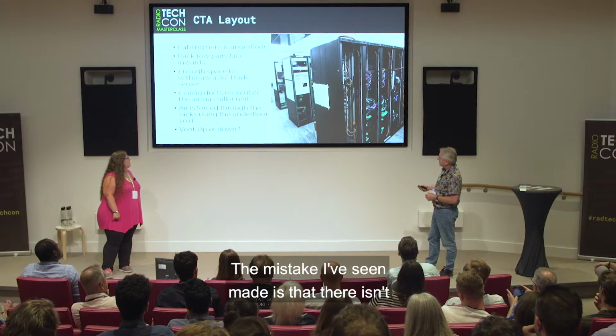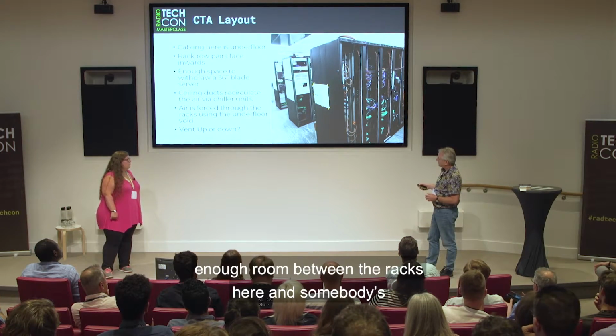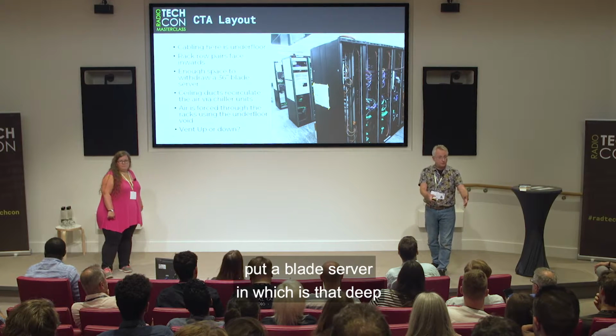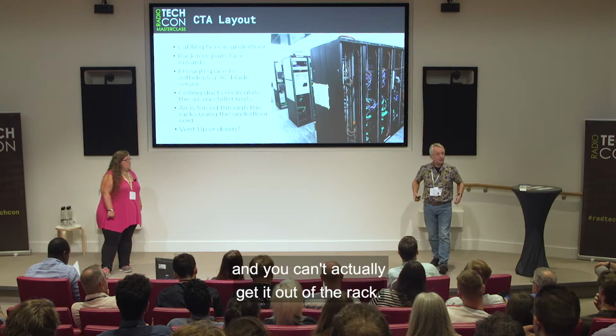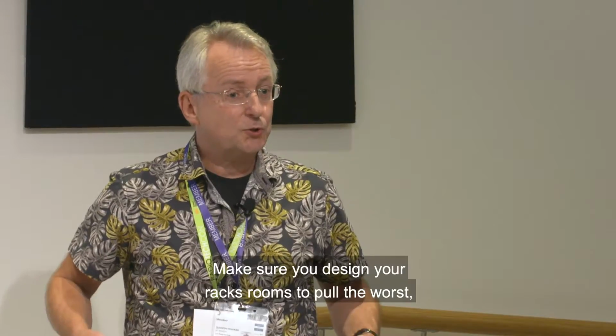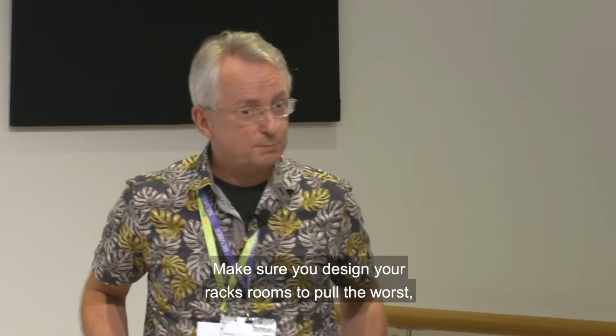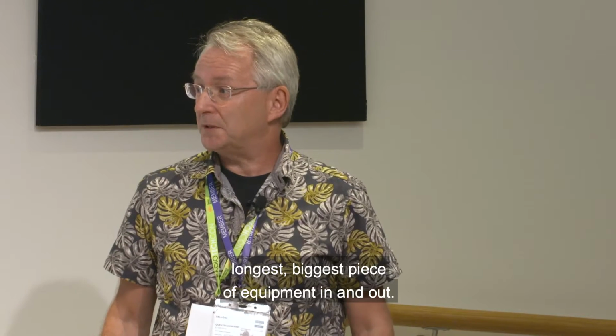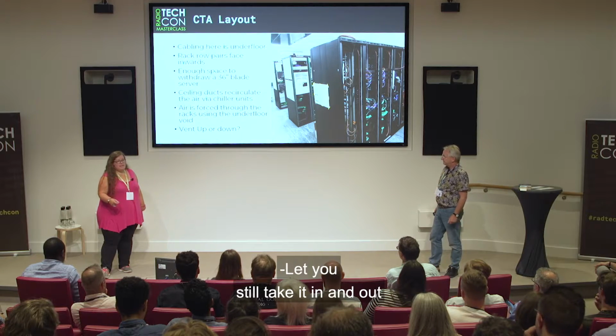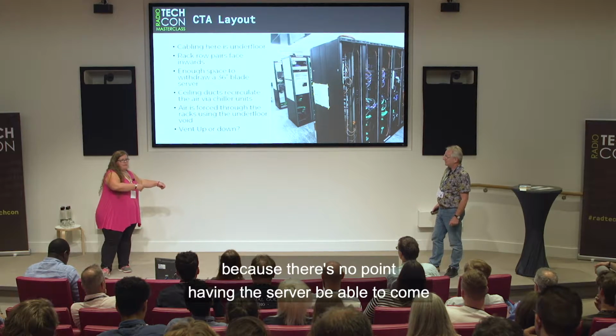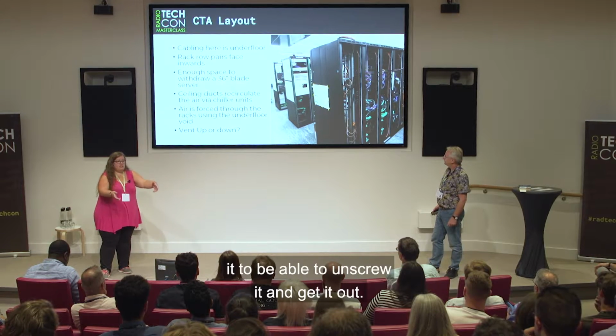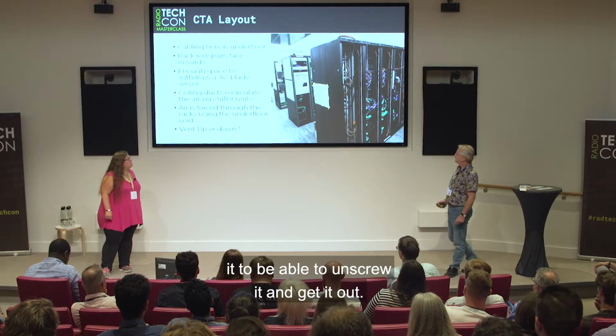A mistake I've seen made is that there isn't enough room between the racks here, and somebody's put a blade server in that's that deep, and you can't actually get it out of the rack. So make sure you design your racks rooms to pull the worst, longest, biggest piece of equipment in and out, and still take it in and out - there's no point having the server able to come in and out if you then can't reach it to unscrew it and get it out.